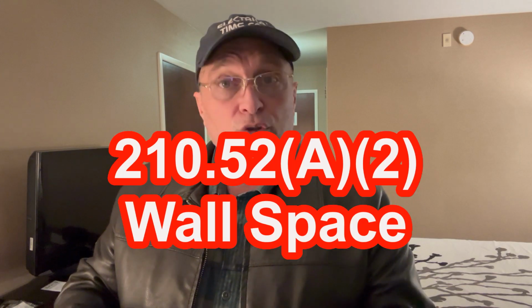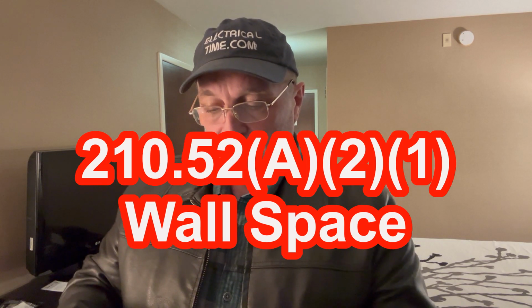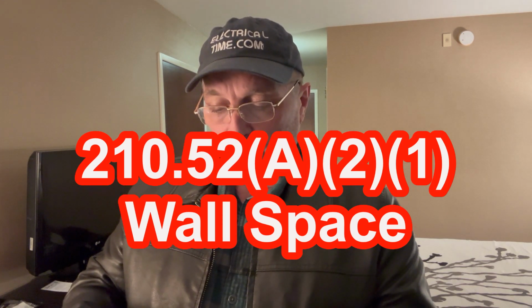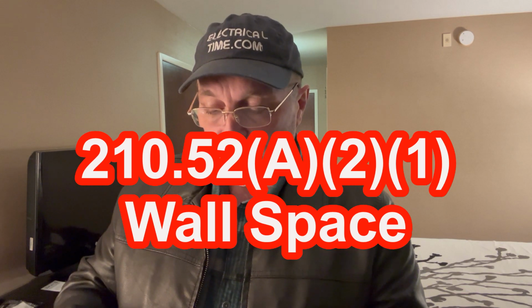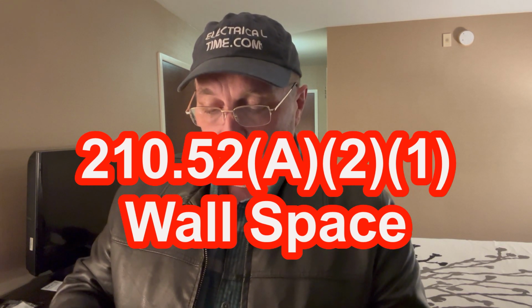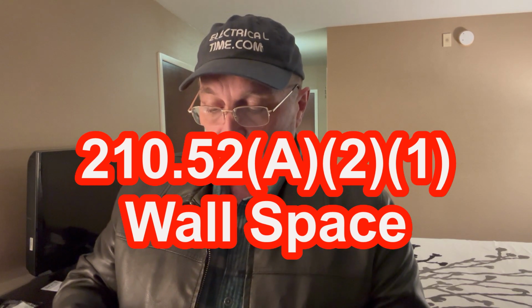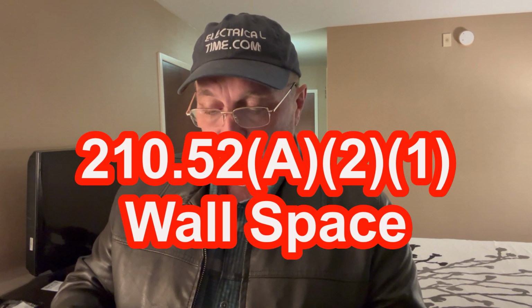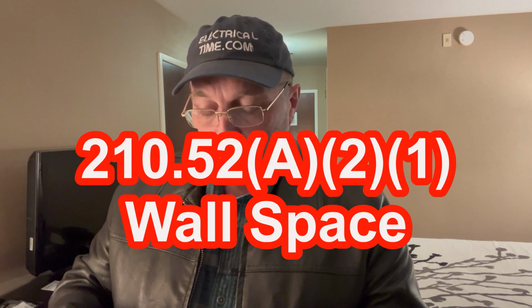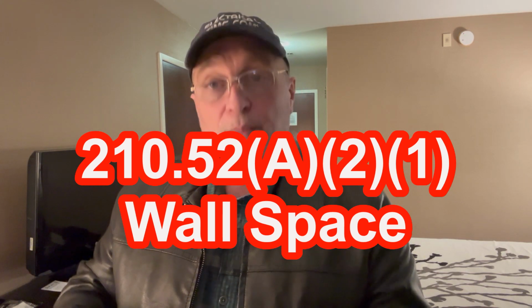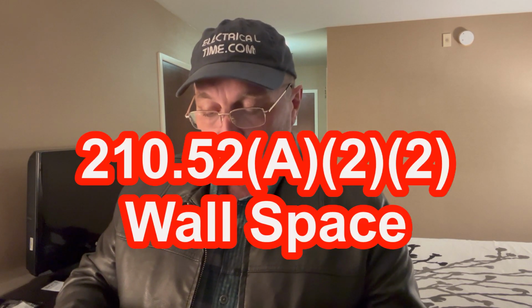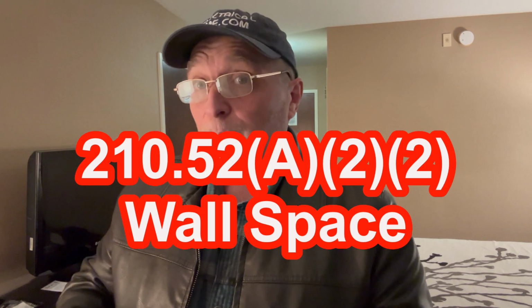All right. A2 is called wall space, and that says, as used in this section, a wall space shall include the following. 1, any space 2 feet or more in width, including space measured around the corners and unbroken along the floor line by doorways and similar openings, fireplaces, stationary appliances, and fixed cabinets that do not have countertops or similar work surfaces. 2, the space occupied by fixed panels and walls excluding sliding panels.